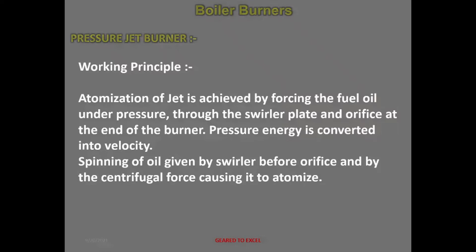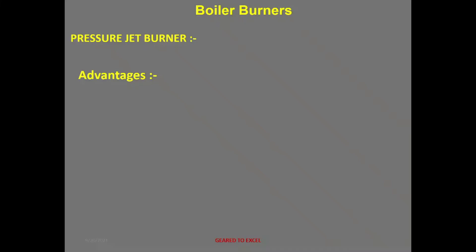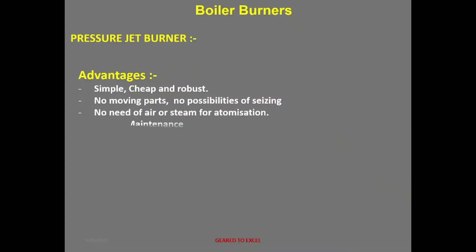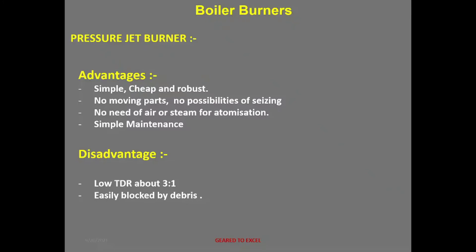Advantages of pressure jet burners: simple, cheap, and robust; no moving parts, so there is no possibility of seizing; no need for air or steam for atomization; simple to maintain. Disadvantages: low TDR — turndown ratio is very low at about 3:1; and it is easily blocked by debris, as the orifice may get clogged due to carbonization or fuel carrying debris if fuel quality is not good.